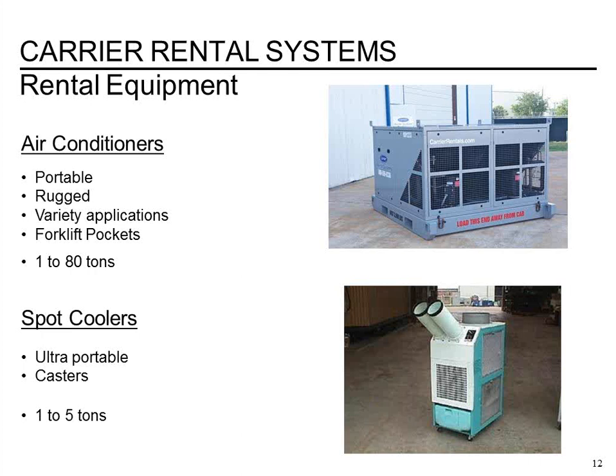Small units. One unique thing that we do offer in the spot cooler that not a lot of people know about, not everybody offers, is we do have water-cooled units, which seem to be increasing in popularity. For instance, if we have a 5-ton unit, it'll connect up to essentially a garden hose, a city water tap. It'll use a water regulating valve to control the water flow. The water will go to waste for the condenser, but ultimately you're able to reject the heat from the space and cool the space without a duct plenum or getting some form of outside air for the condenser for the unit. And those are great for different applications inside a building where it's hard to reject that heat.